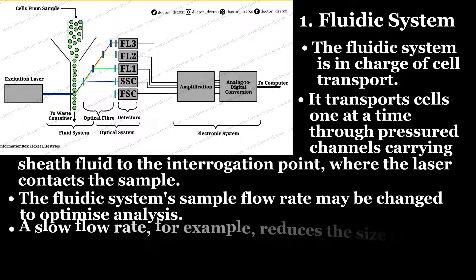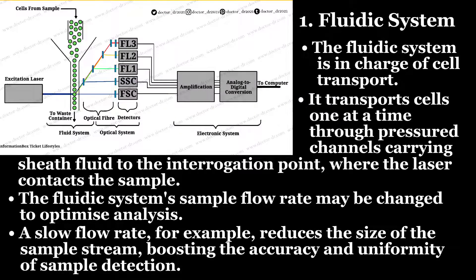The fluidic system's sample flow rate may be changed to optimize analysis. A slow flow rate, for example, reduces the size of the sample stream, boosting the accuracy and uniformity of the sample detection.